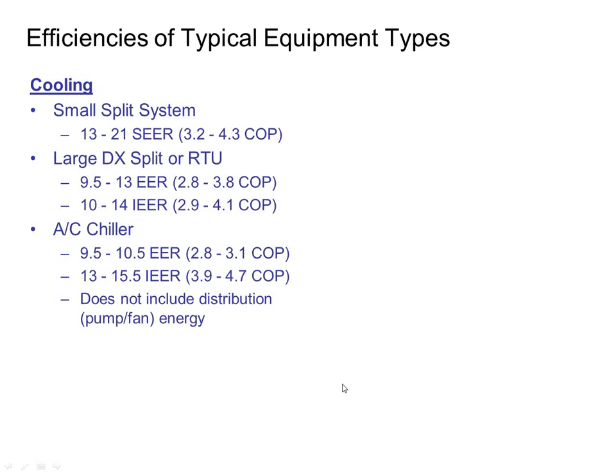However, with all that being said, what I try to do with some of these rating systems is I try to convert them to an approximate equivalent COP. So we can kind of compare them just on a discussion basis. So for small split systems that are 65,000 BTUs or less, which is 5 tons, those systems are typically rated with SEER, S-E-E-R, which is the residential rating system, even though I know we use 3, 4, and 5 ton systems commercially. And even packaged rooftops are rated with SEER, 5 tons and under. You can see the COP range for cooling is that 3.5 to 4.5 type range.